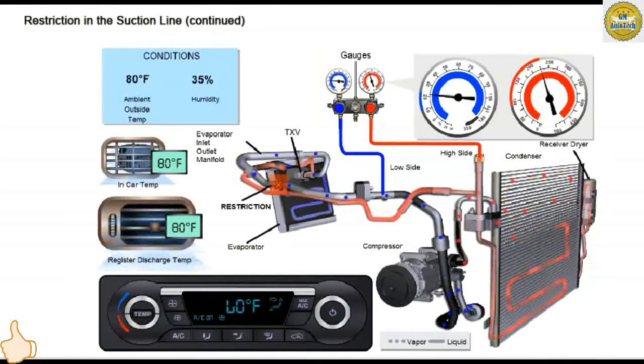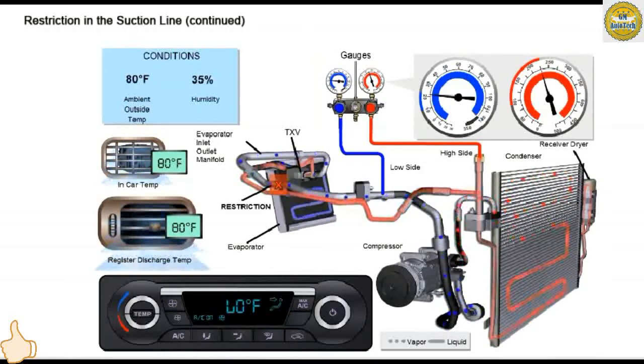A restriction in the suction line between the evaporator and low-side service port causes the high side pressure to be normal to low, and the low side pressure will be low.